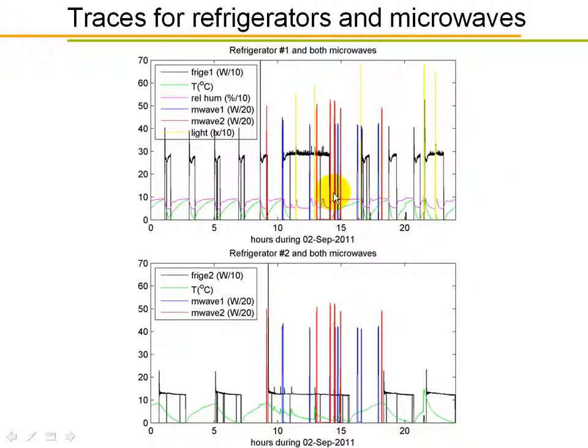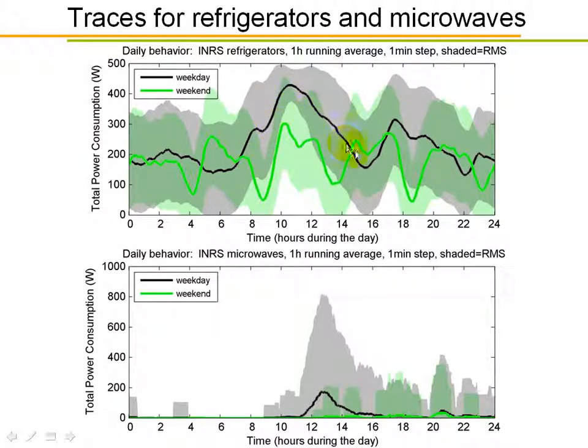The human interaction with the refrigerators raises the temperature inside, meaning longer power on periods at lunchtime and some perturbation of the regular cooling cycle in the mornings and evenings. From the temperature evolution behavior, one can conclude that the refrigerators could afford being 2-3 hours off. Looking now at those aspects in the averages, the human behavior suggests that we may switch off refrigerators between 12 and 2:30 p.m. while there is a microwave peak, in order to shift some load.